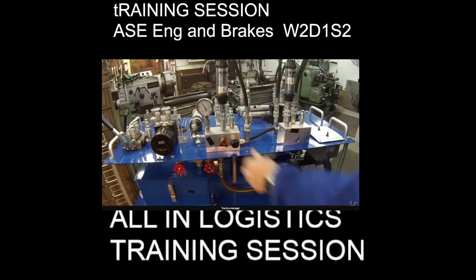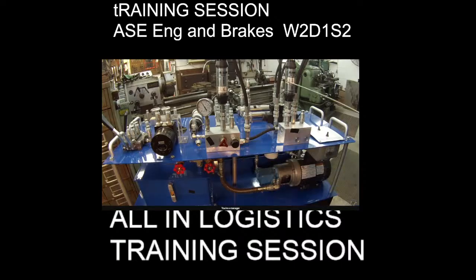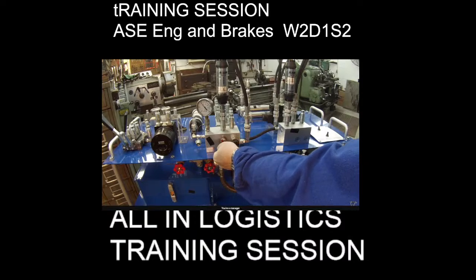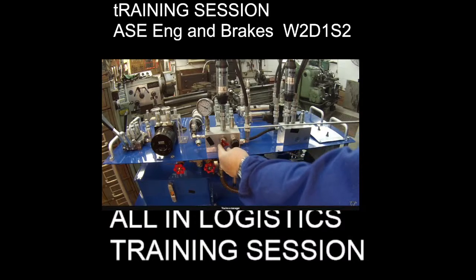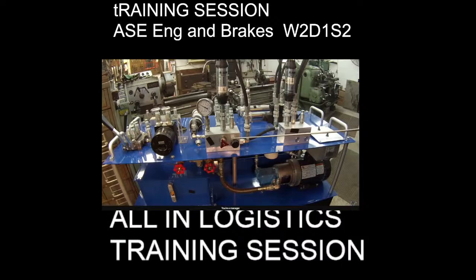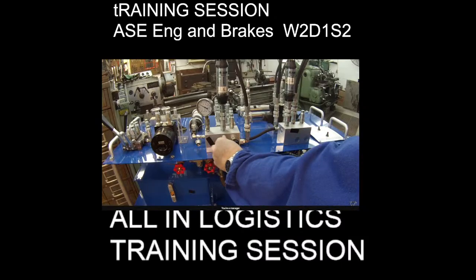So what I'm going to do is prove to you pumps don't pump pressure. I'm pumping 1.8 gallons per minute right here. What you'll see is that pressure drop, it's not having to go over this relief valve right here. As I open that up more and more and more, you see the pressure drops down. And now I'm going to open it all the way up.